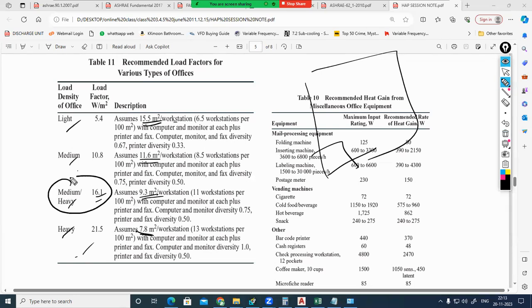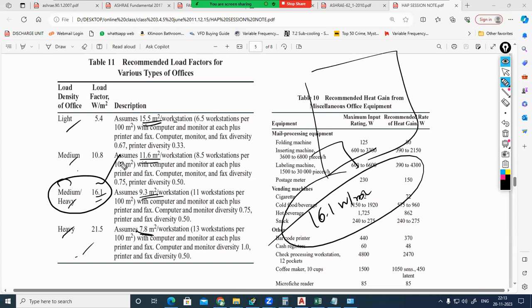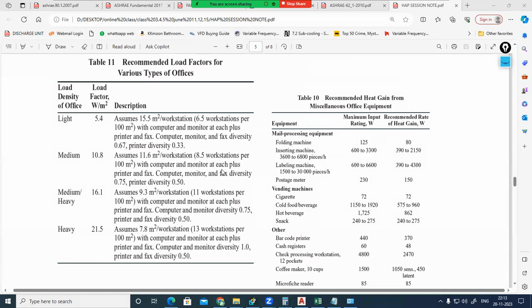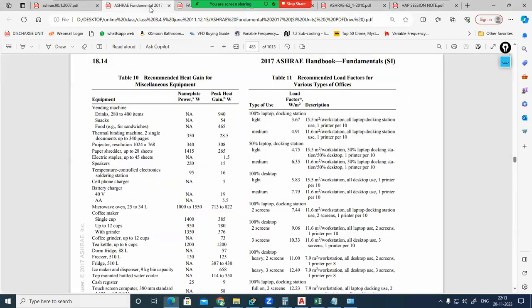Normally, we will be selecting the medium heavy case, which means 16.1 watt per meter square for our design. Accordingly, only we will be designing it. When you are going to the Revit software for heating and cooling load analysis, the Revit software is also preset with the same value of 16.1 watt per meter square, now also. This was the older table and this one is the newer table, but more precise it is.